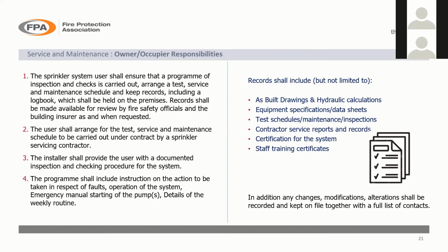These should be held on the premises in the form of records, and these can be made available for review by fire safety officials and also by people carrying out audits on the system, such as during the third-party inspections. Typically, if you've got a building where a sprinkler system is installed, you will probably have a weekly test log sheet where you test all your pumps and your valve sets, and you write down how long it takes to ring the bell, that kind of thing.